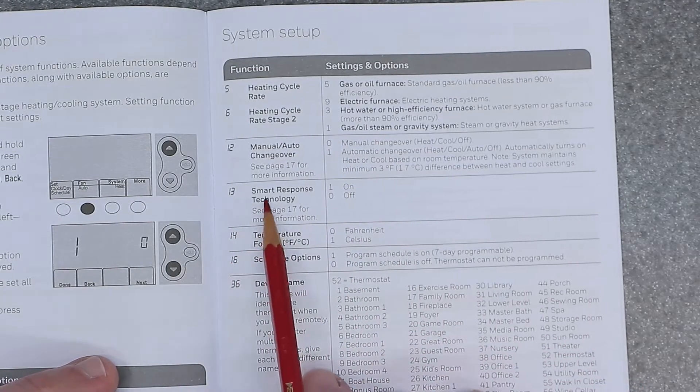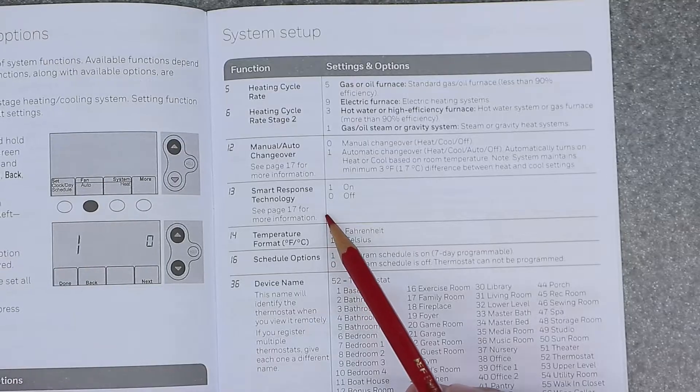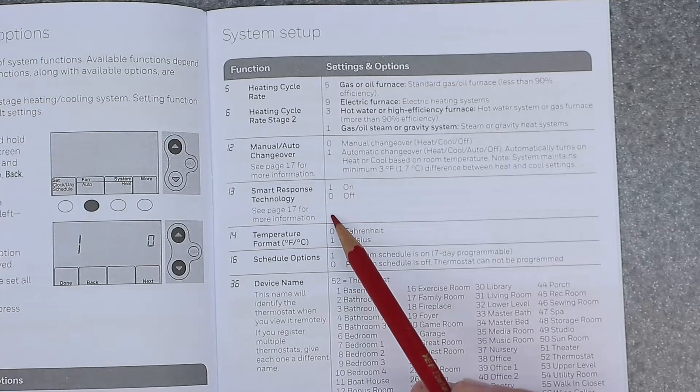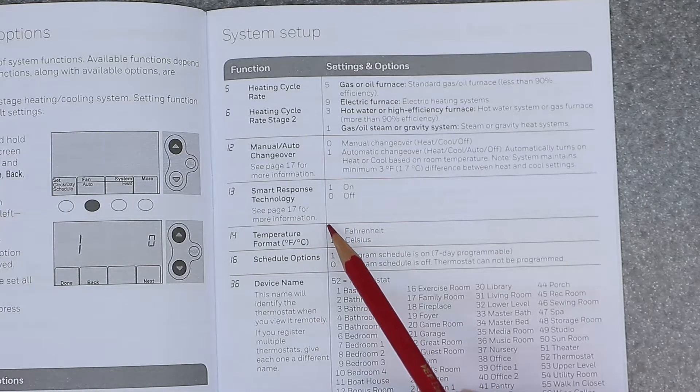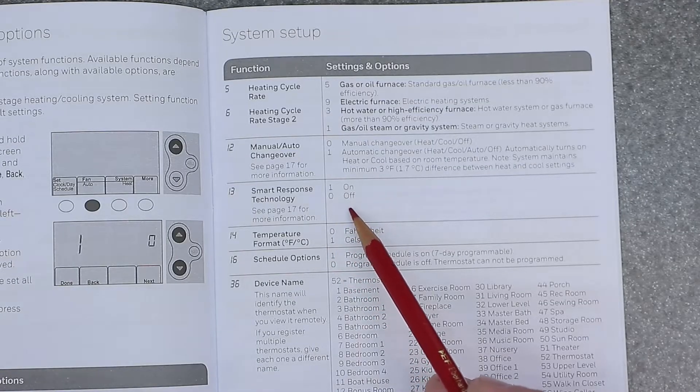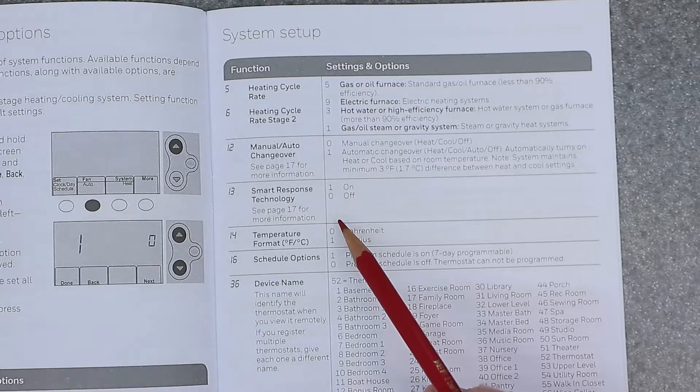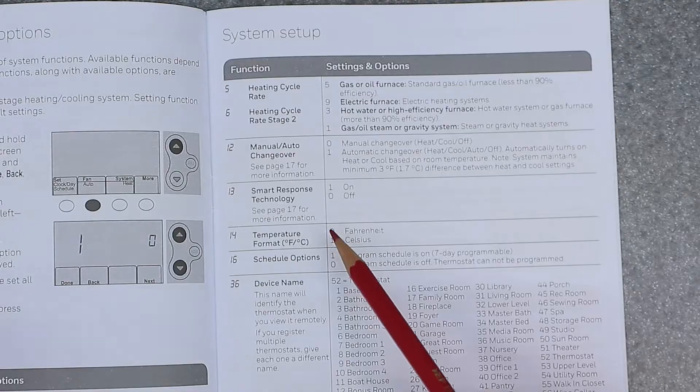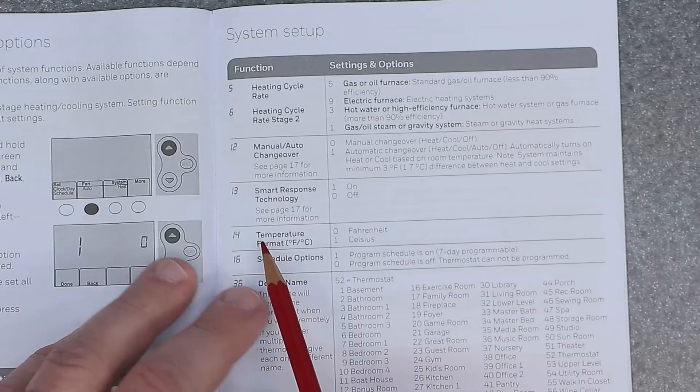Thirteen is smart response technology. One is going to equal on and zero is going to be equal off. So this here will actually learn how long it takes for your room to come up to temperature. So this usually will start the heat early or start the cooling early as well. Some people don't like this because it makes the system run longer and start earlier. So most of the time people will deactivate this and turn it off. But it will start the system an hour or two ahead of time that's scheduled in order to compensate for that time for it to be that exact temperature if you get what I'm saying. So if that's something you want, decide that and go ahead and change that over to on or off.